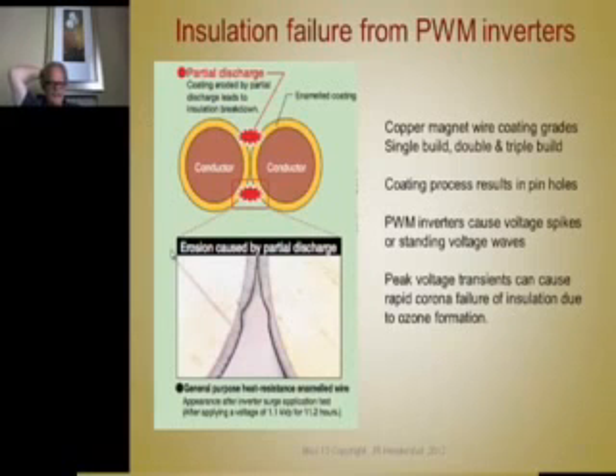There's a well-documented, well-known failure mode of stator phase windings when they're driven with inverters. And since we're discussing the design of electric machines that are driven by inverters rather than grid power, we have to bring this subject up and talk about this.